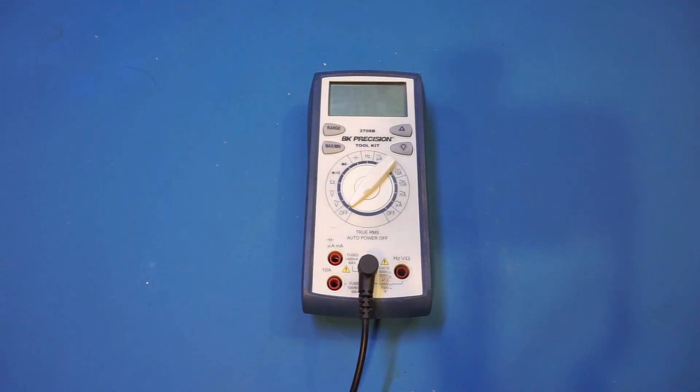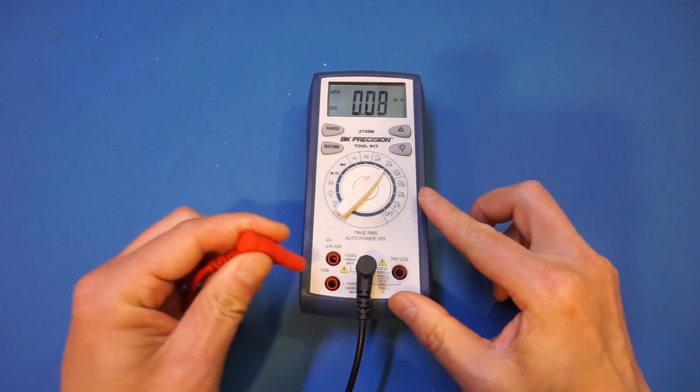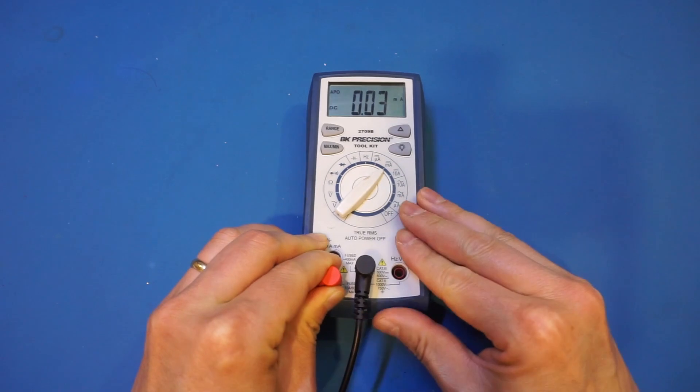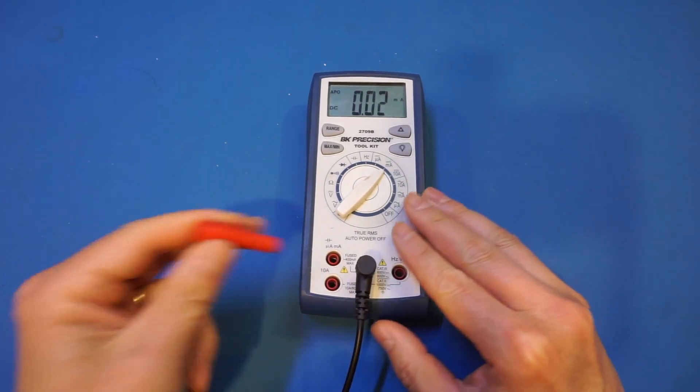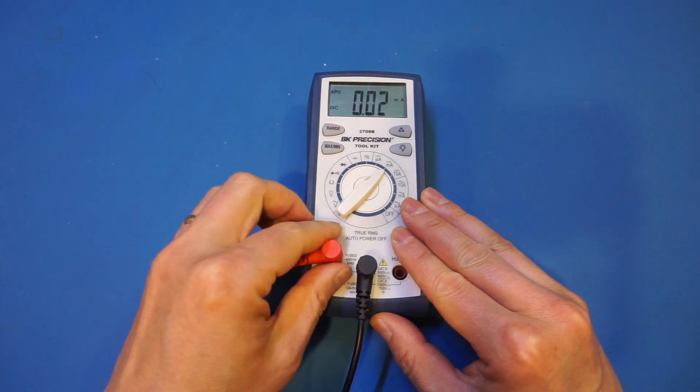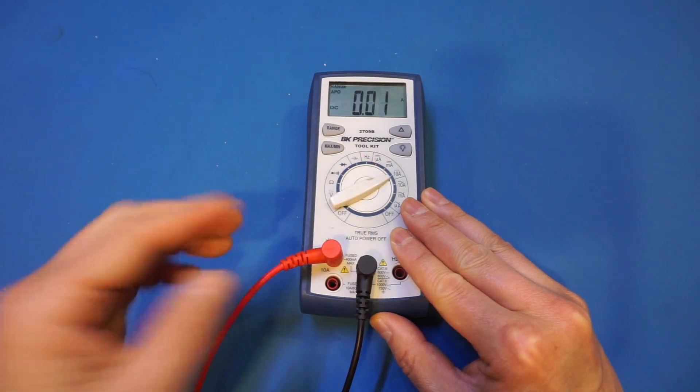My BK2709B has a split input jack design. While it doesn't prevent you from physically inserting the probe into the wrong jack for the intended range, you do get a very loud audible warning if the probe is in the wrong jack. So let me demonstrate here. Let me put it into milliamp range, and let's plug it into the amp jack. You'll hear this very loud warning telling you that you're in the wrong jack here. So let me, of course, put it into the milliamp jack and everything is working great. And vice versa, if I now change it to 10 amp range, you'll hear this warning again because we're in the wrong jack.